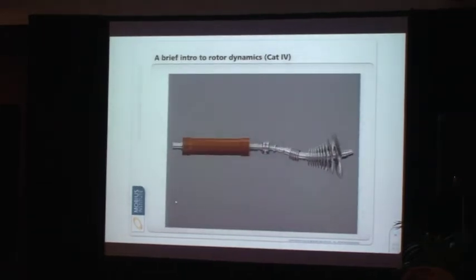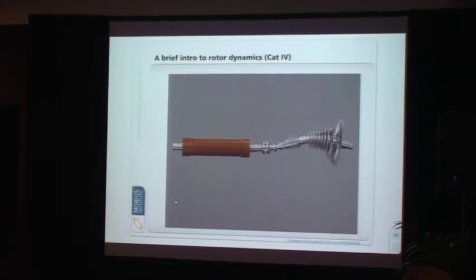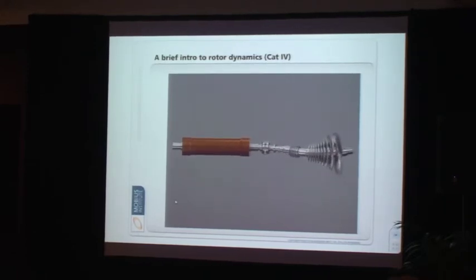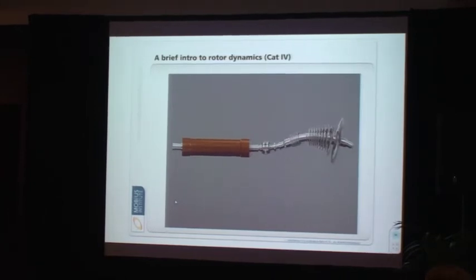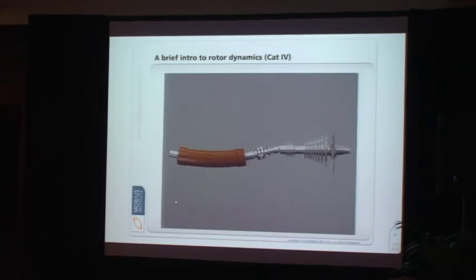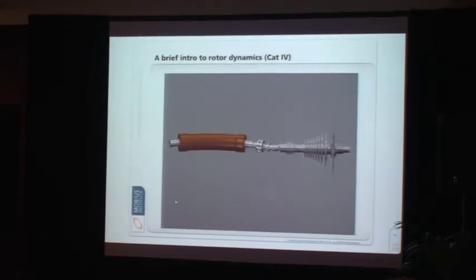But we've got to remember that we've actually coupled this thing up to a generator, and so now we're dealing with the whole machine. What we're actually seeing is, we went through the process of modelling this whole thing to see exactly how it would vibrate at different frequencies and so on. There we've got the first bending mode of the steam turbine, and you can see the generator is just spinning happily. But at a different speed, the generator is going through its first bending mode, and the turbine is happy.